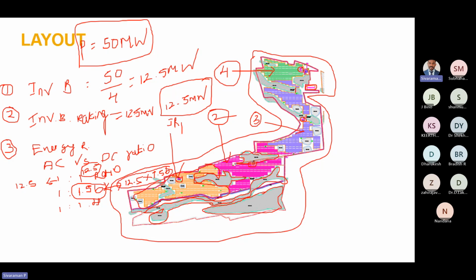So it means that to maintain this 1 to 1.56 DC ratio, we have to install 12.5 multiplied by 1.56. Whatever value comes, that much power capacity of solar PV panels we have to install. Okay, so why do we have to go for 1:1 versus 1:1.56?